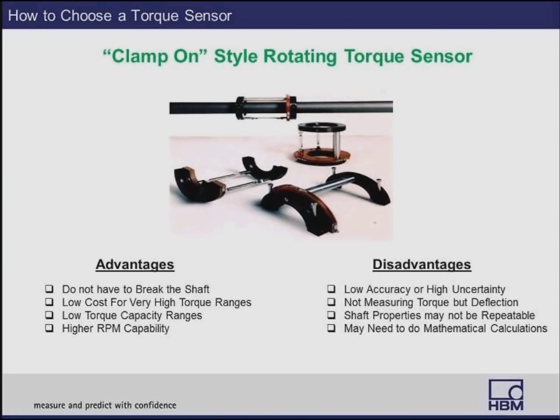Clamp-on style torque sensors are generally used when breaking the shaft and inserting an inline torque sensor is not feasible. The advantage is very low cost for very high torque ranges — for example, clamping onto a shaft that is a foot or two feet in diameter is much easier than inserting a rotating sensor. They also offer very low capacity ranges and higher RPM capabilities. The disadvantage is that you're not actually measuring torque but deflection in the shaft. You must know the shaft's manufacturing properties to do mathematical calculations to obtain an accurate torque reading. These sensors are used more for convenience than for applications requiring high accuracy.